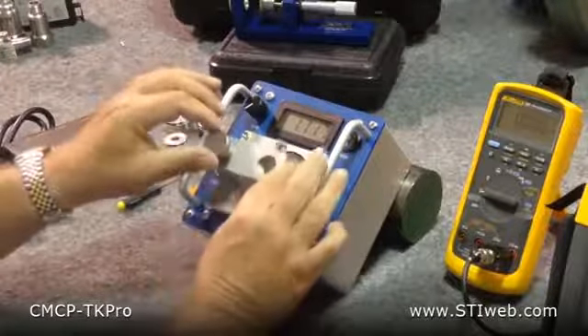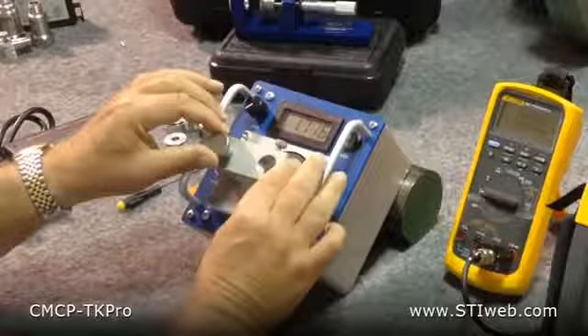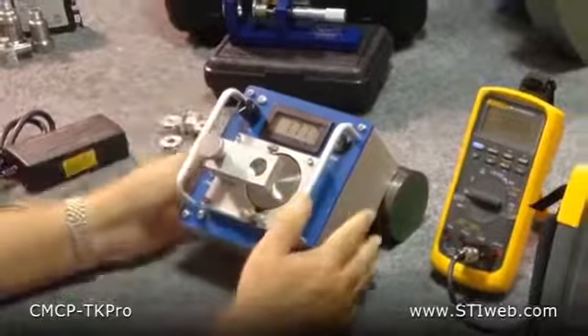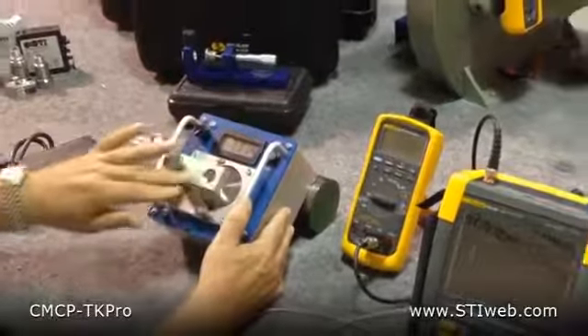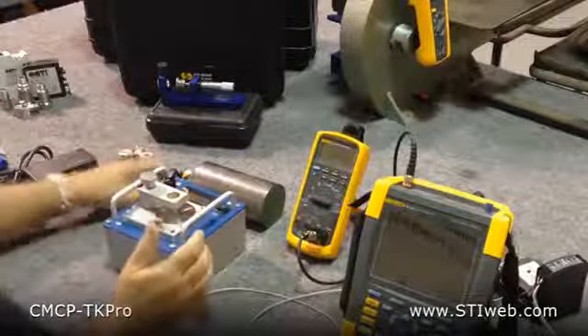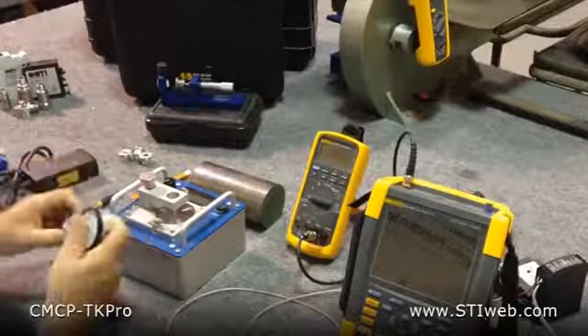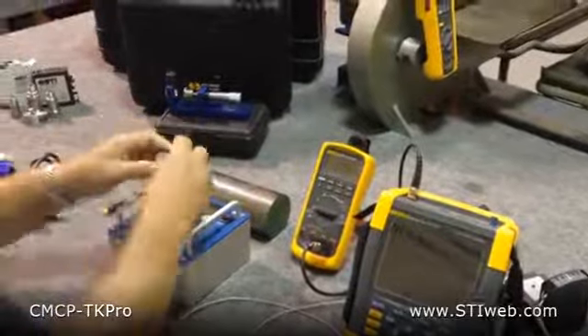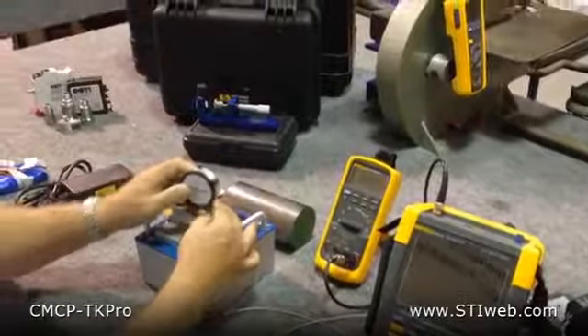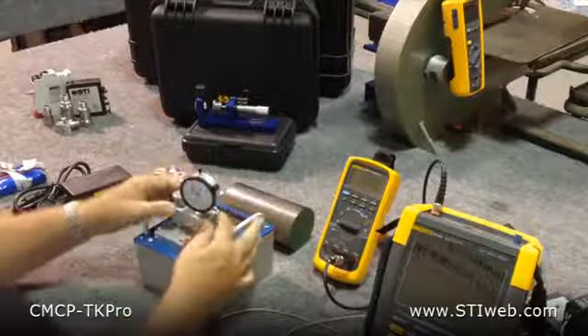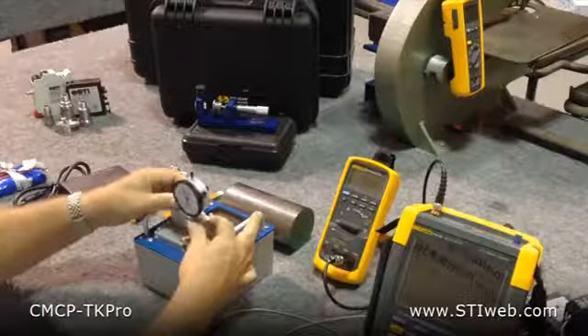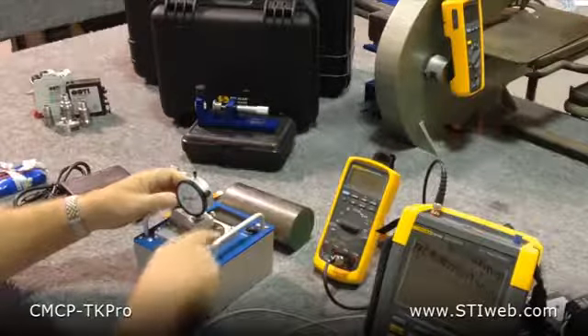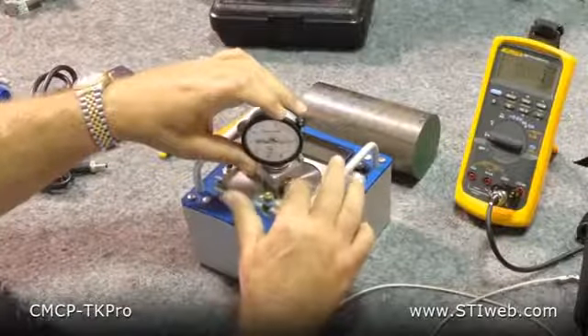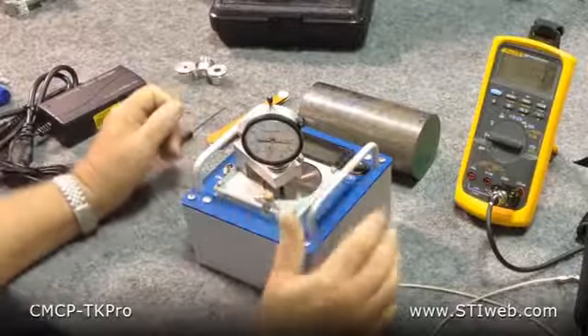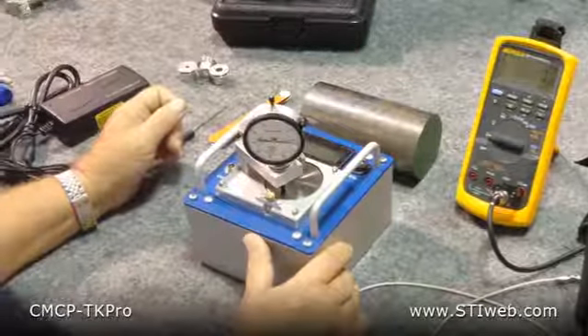And the swing arm is used to adjust where on the wobble plate the eddy probe or dial micrometer is looking. Okay, what we're going to do first is set the swing arm using the dial indicator. We do that by using the proper collet. Then we mount the dial indicator into the swing arm. Now, we can change the amount of vibration it sees by swinging where the dial indicator sees the wobble plate. So right now I'm getting 11, almost 12 mils of vibration where I'm adjusted.